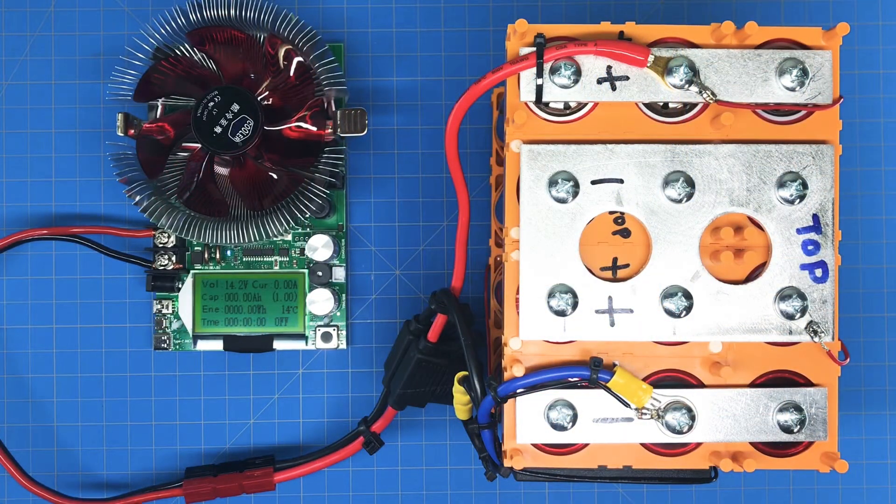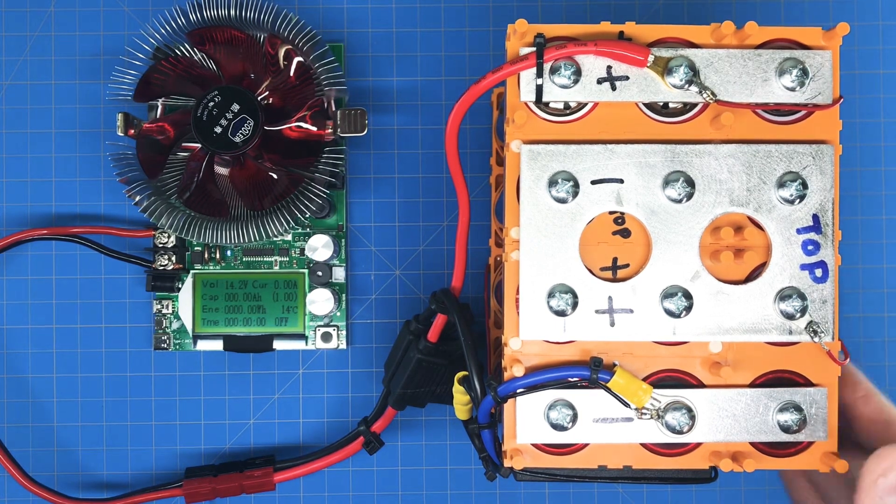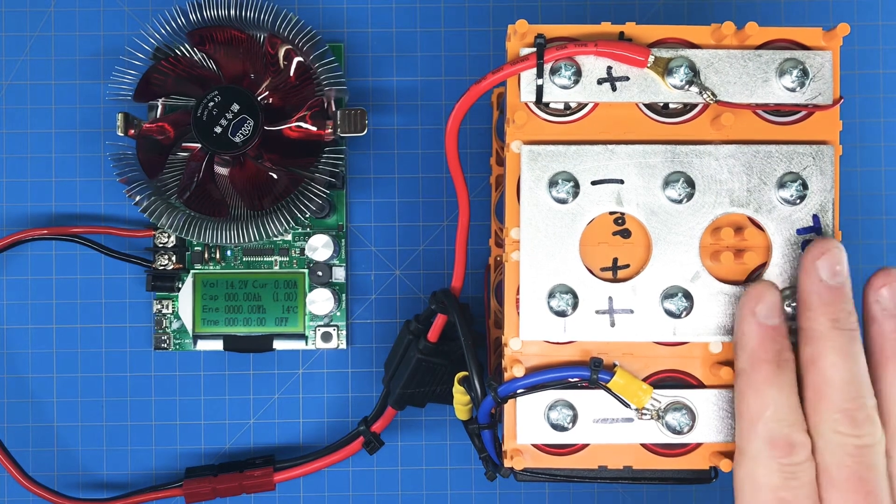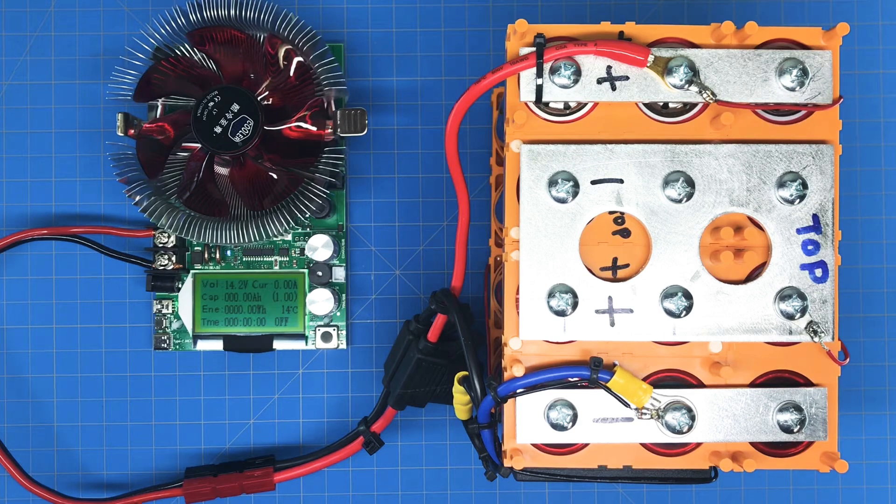We're all set up for the capacity check of this completed battery. If these cells were brand new with this setup, we'd be expecting about 24 amp hours at 14.6 volts.